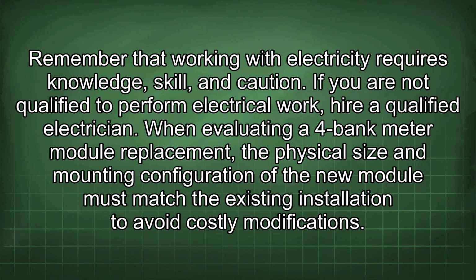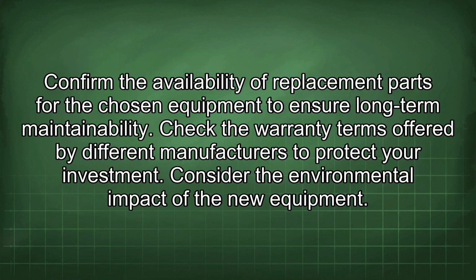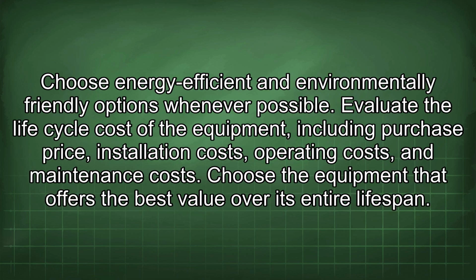When evaluating a 4-bank meter module replacement, the physical size and mounting configuration of the new module must match the existing installation to avoid costly modifications. Confirm the availability of replacement parts for the chosen equipment to ensure long-term maintainability. Check the warranty terms offered by different manufacturers to protect your investment. Consider the environmental impact of the new equipment. Choose energy-efficient and environmentally friendly options whenever possible.